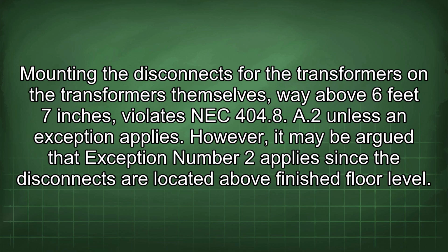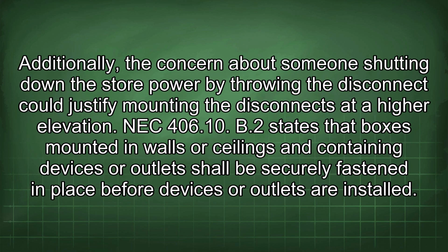However, it may be argued that exception number 2 applies since the disconnects are located above finished floor level. Additionally, the concern about someone shutting down the store power by throwing a disconnect could justify mounting the disconnects at a higher elevation. NEC 406.10.B2 states that boxes mounted in walls or ceilings and containing devices or outlets shall be securely fastened in place before devices or outlets are installed.